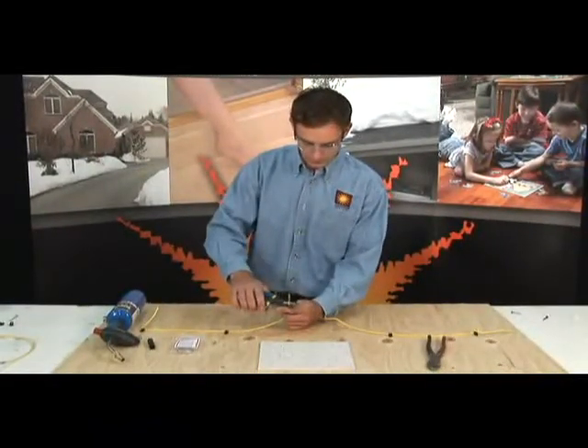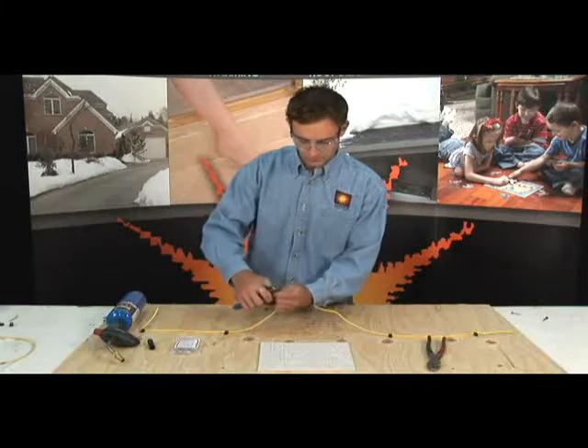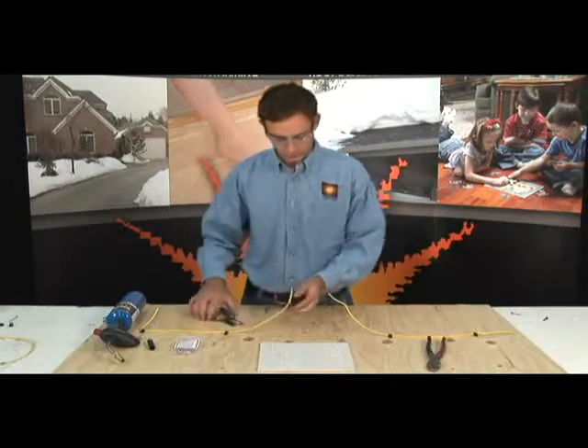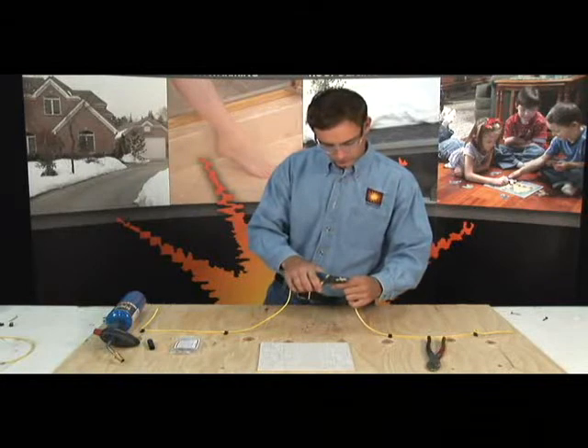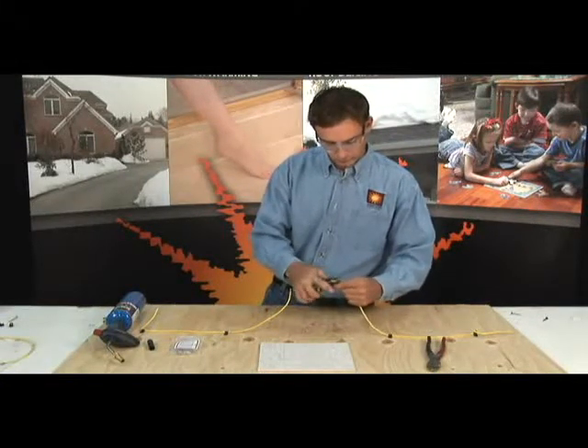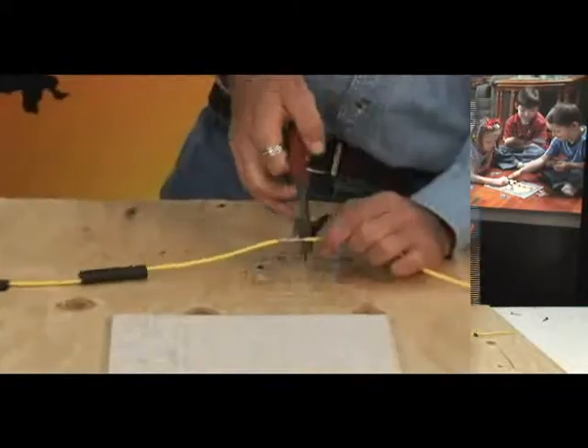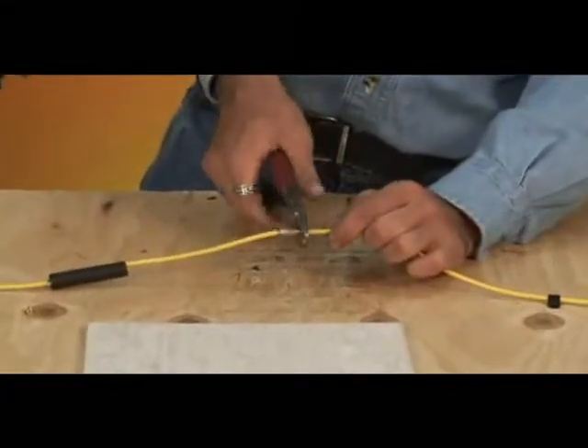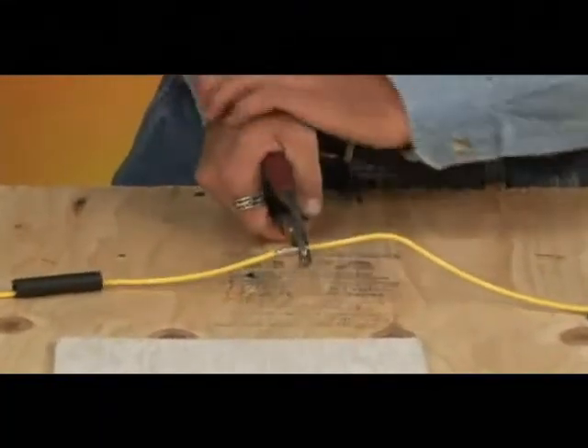Tough cable splicing is accomplished by sliding the provided heat shrink at least 8 inches beyond the splice, then stripping back the insulation on the wires to be spliced 1 inch. Next, insert the tough cable into the number 10 butt splice connector.